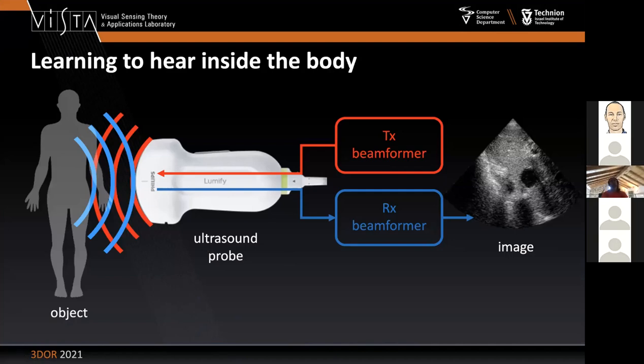In ultrasound, the image is acquired by sending an acoustic pulse which bounces back from discontinuities in acoustic impedance. We receive this echo and form the image. Typically the same device is used for transmitting and receiving, with no moving parts — just a phased array of ultrasonic transducers that, by delaying and summing multiple lines of signals, creates a focused beam that sweeps the scene. On the way back, the same way we form the transmit beam with a beam former, we form the image with a receive beam. It's straightforward signal processing.